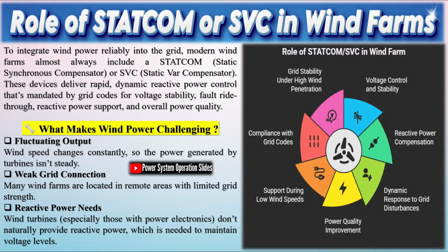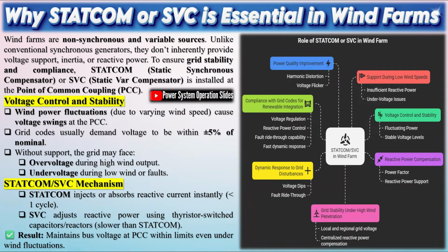Unlike these older technologies, Statcoms are capable of responding to fast-changing reactive power demands and highly dynamic loads with precision and speed. The term synchronous in Statcom refers to its ability to generate or absorb reactive power in real time, synchronized with the grid's voltage and frequency conditions. This synchronous operation allows Statcoms to stabilize voltage levels effectively, making them indispensable in systems where reactive power demand fluctuates rapidly. Their real-time responsiveness ensures that voltage remains within acceptable limits, even under challenging load conditions or during disturbances.